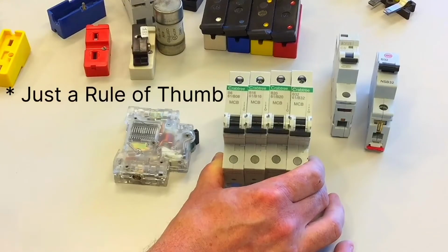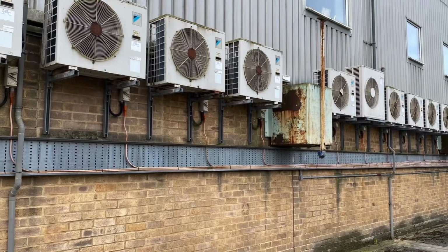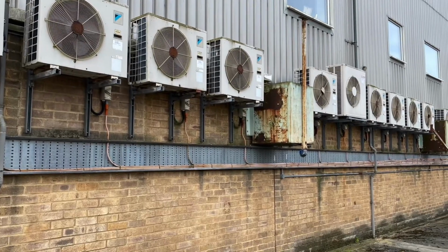quickly, domestically, you'd have a B-type circuit breaker. Where there's lots of inductive loads, such as a commercial office, you'd probably have a C-type circuit breaker. Where you have highly inductive loads like welding equipment, some air conditioning units, you'd have a D-type circuit breaker. We'll add a little bit more detail as we move through the course on those.